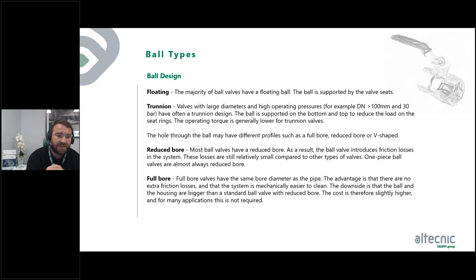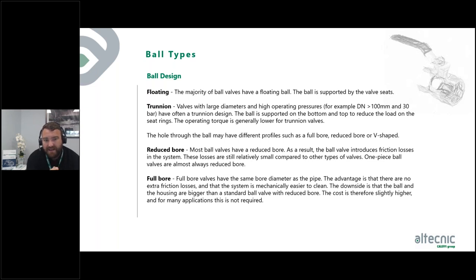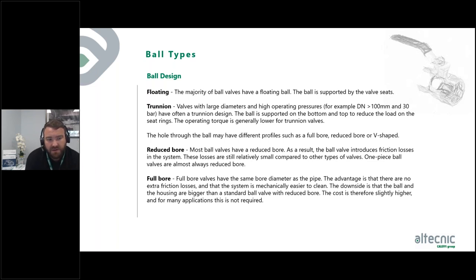A full bore ball valve has the same bore diameter as the pipe. So if you've got a 15mm or half-inch pipe, the internal diameter of the ball matches the pipe exactly. The advantage is there are no friction losses and the system is mechanically easier to clean. The downside is that the ball and housing are slightly bigger, making the cost slightly higher. However, there is a big benefit in terms of flow through the system and reducing head loss.